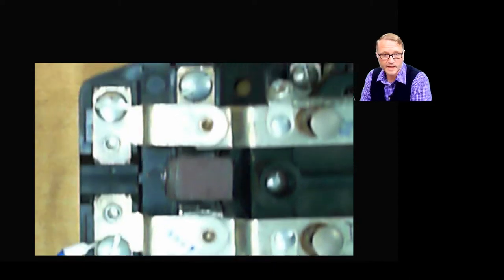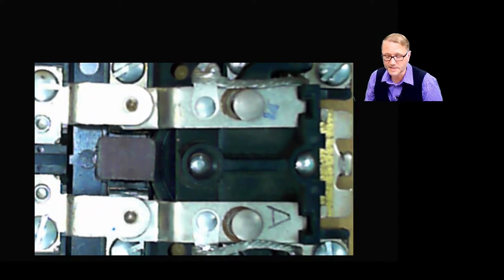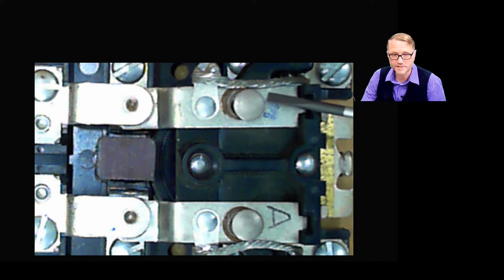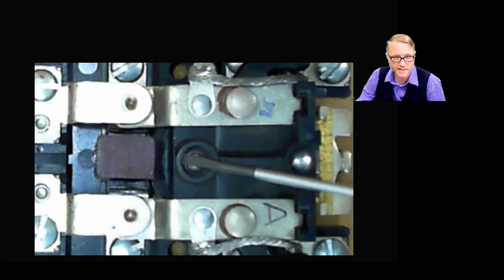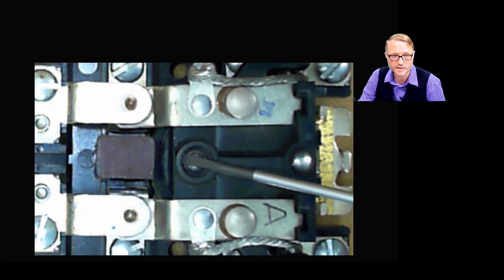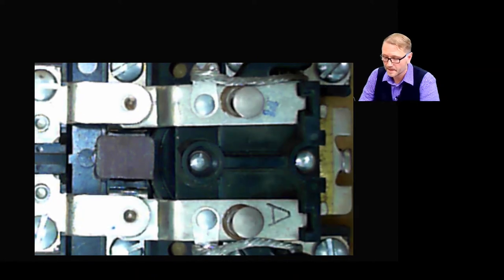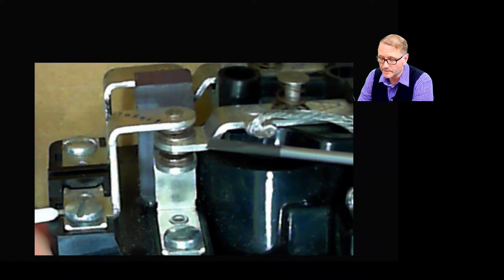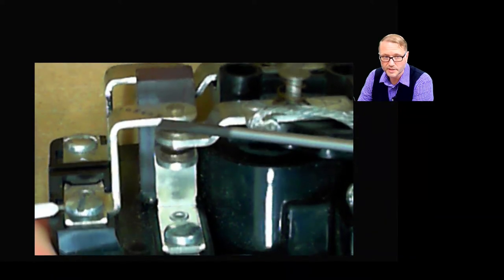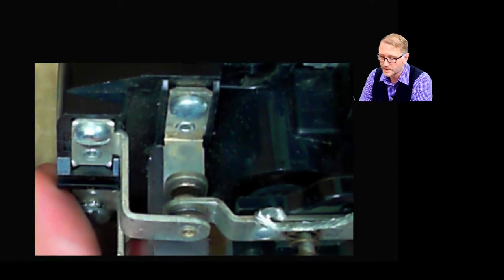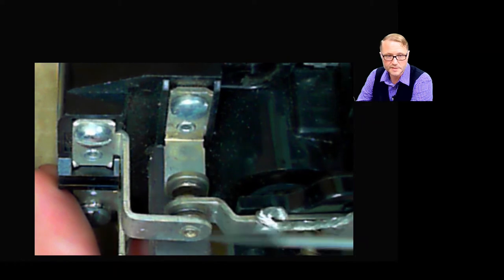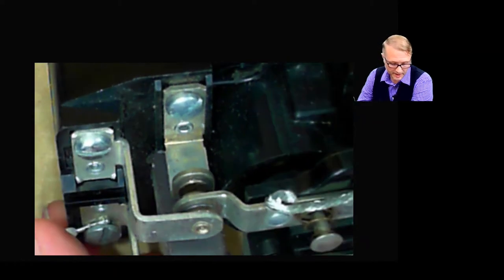This relay actually has two pairs of contacts. We would call these poles. So here's the A pole and here's the B pole. You can see that they are mechanically coupled together on the armature. The A pole has a movable contact, a normally closed, normally open, and the B has independent contacts as well. Here's the movable, here's the normally closed, and there's the normally open contact.